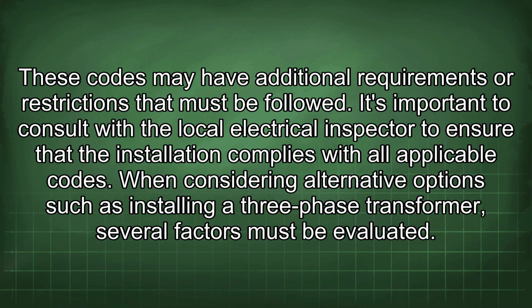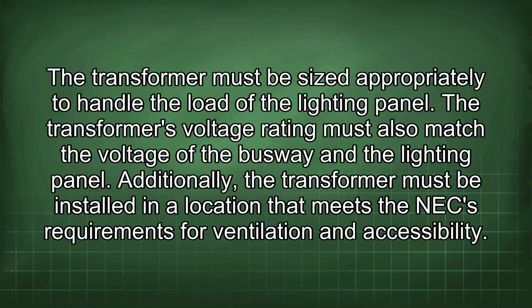These codes may have additional requirements or restrictions that must be followed. It's important to consult with the local electrical inspector to ensure that the installation complies with all applicable codes. When considering alternative options such as installing a three-phase transformer, several factors must be evaluated. The transformer must be sized appropriately to handle the load of the lighting panel. The transformer's voltage rating must also match the voltage of the busway and the lighting panel. Additionally, the transformer must be installed in a location that meets the NEC requirements for ventilation and accessibility.